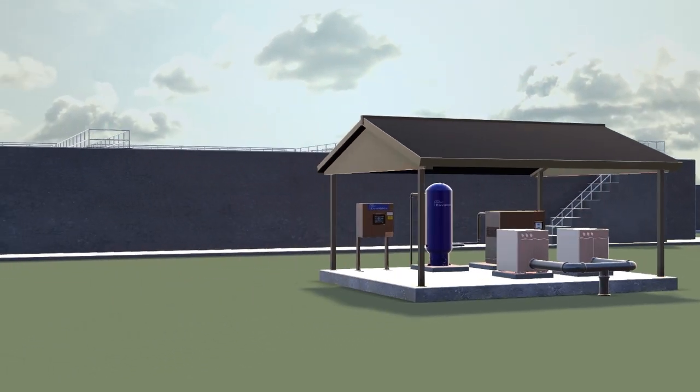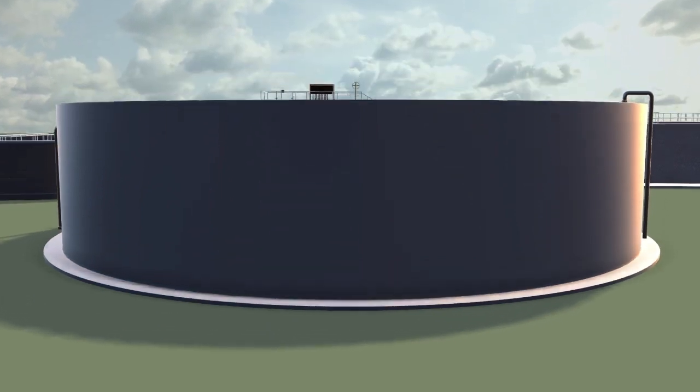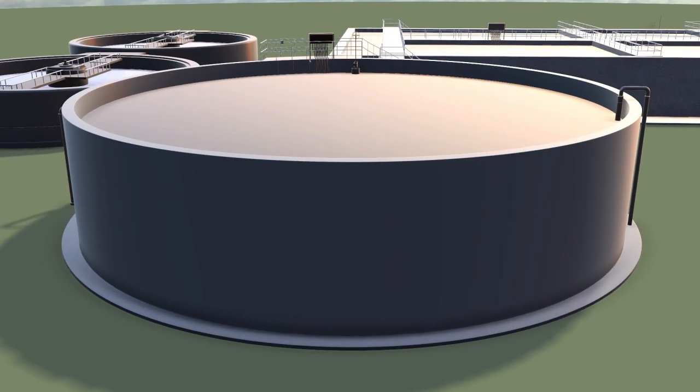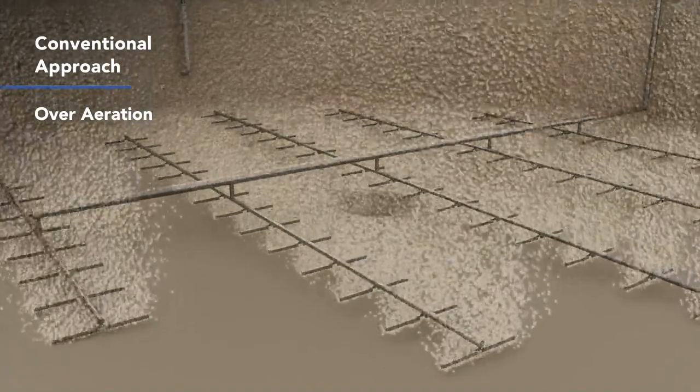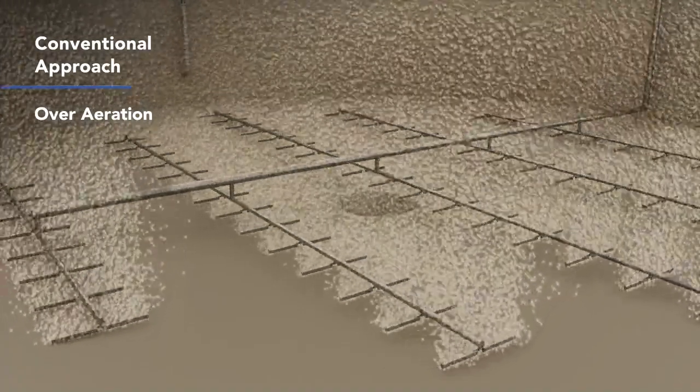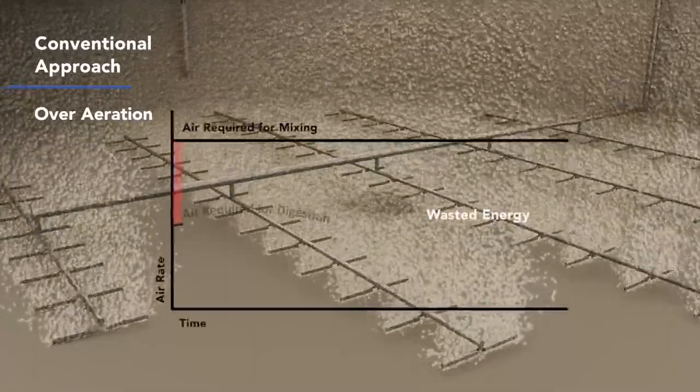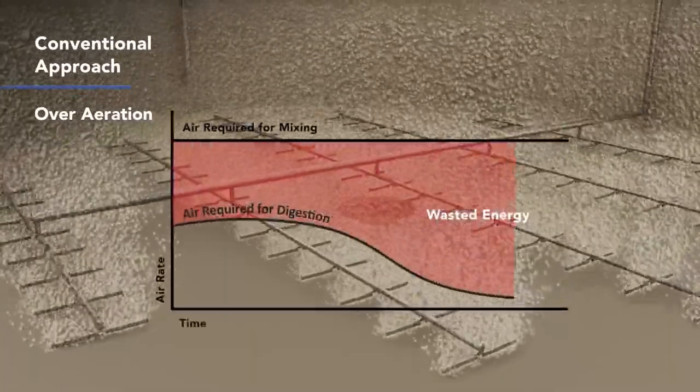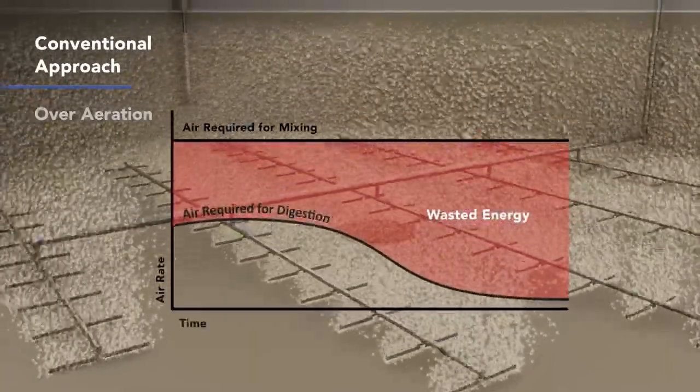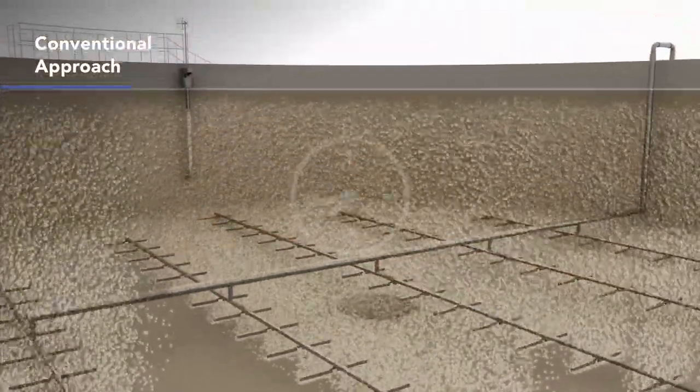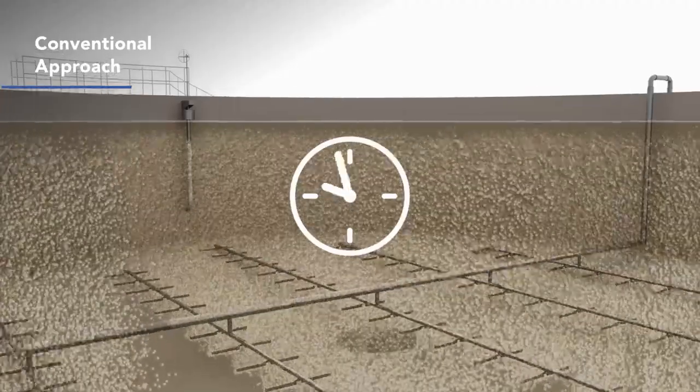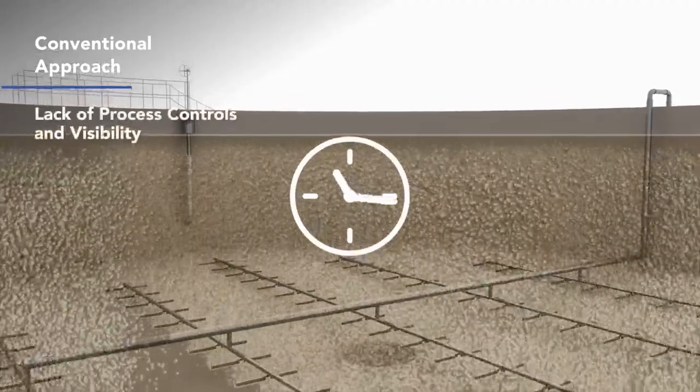With these goals in mind, conventional aerobic digestion creates numerous problems. Let's look at the aeration equipment. The required mixing air rate demands a constant flow of aeration, regardless of biological process needs. In most cases, the mixing airflow is far greater than the oxygen demand. To maintain complete mixing, the conventional aerobic digester aerates 24-7 and offers no flexibility or process control.